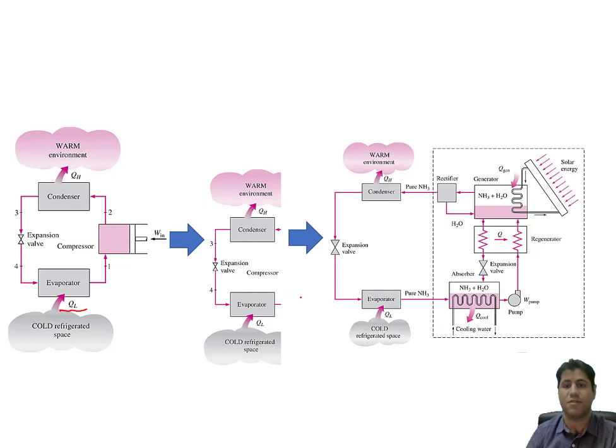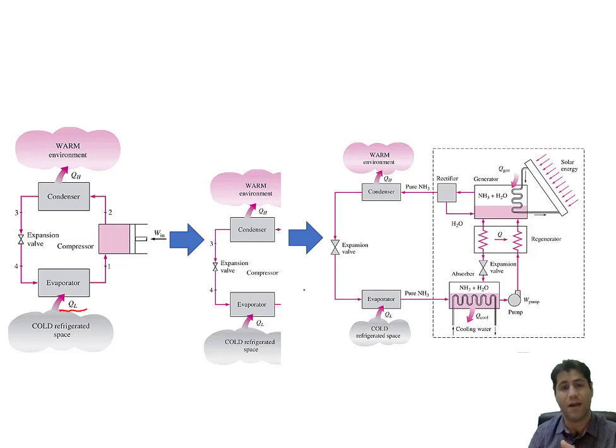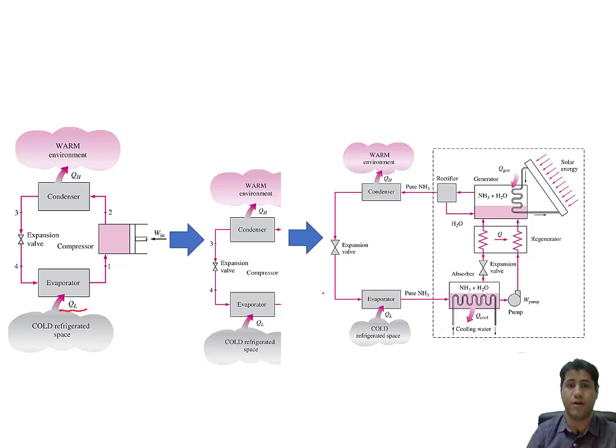In the absorption refrigeration system, we use special working fluids whose phase can be changed using a heat source — by increasing their temperature — rather than direct mechanical compression. The only difference between ARS and the vapor compression cycle is the compressor part. We remove the compressor and replace it with a box. The rest of the cycle is similar to vapor compression.